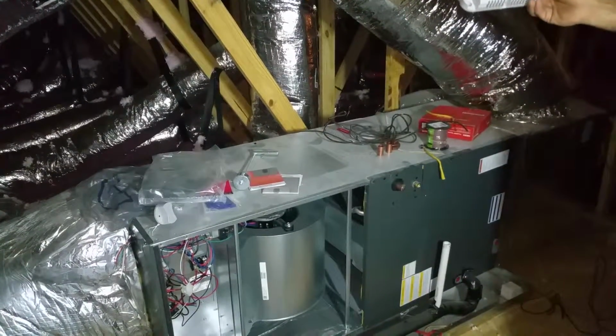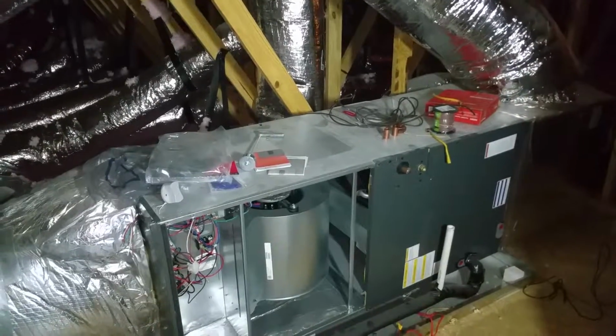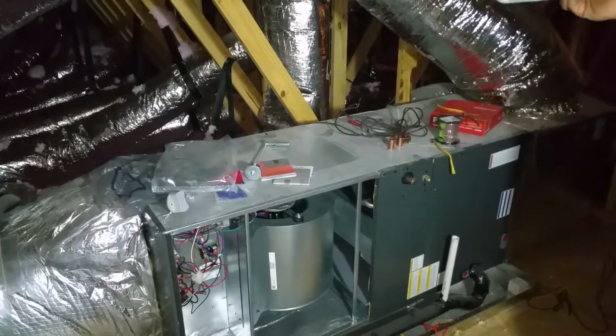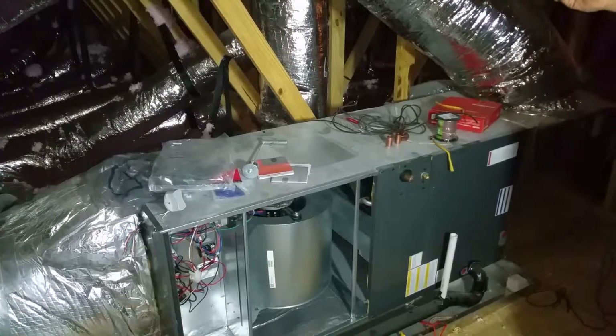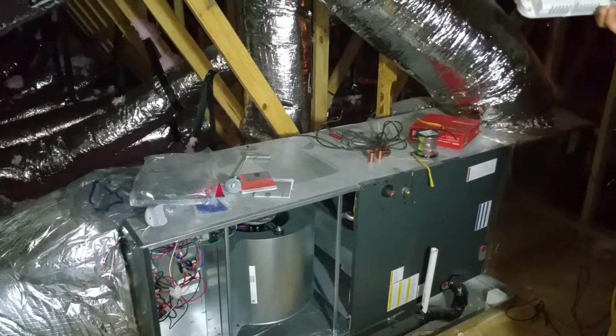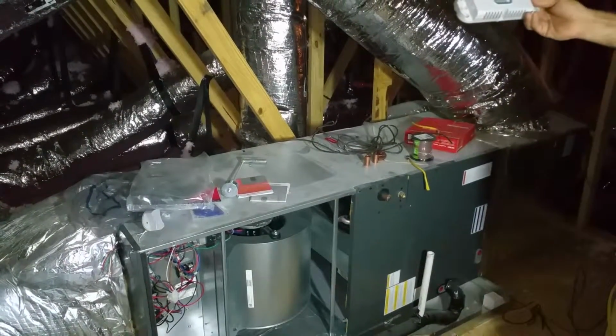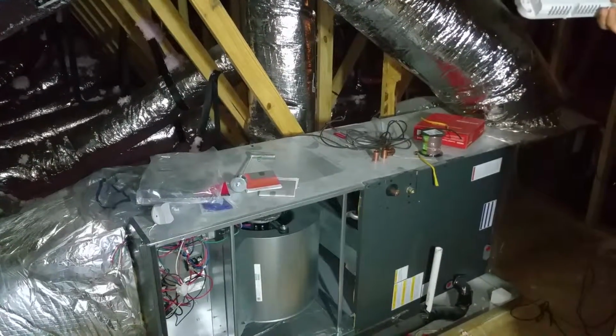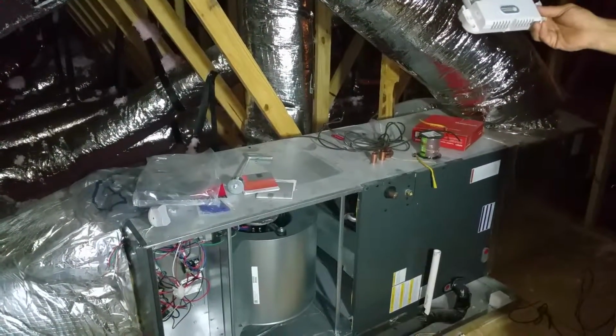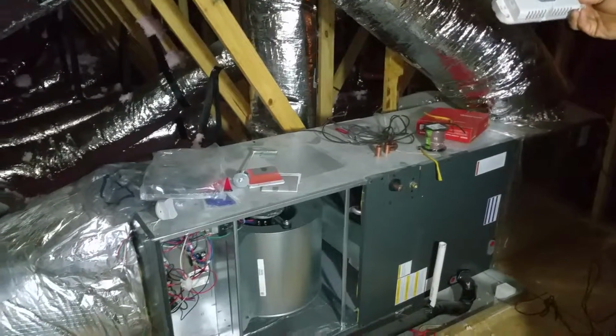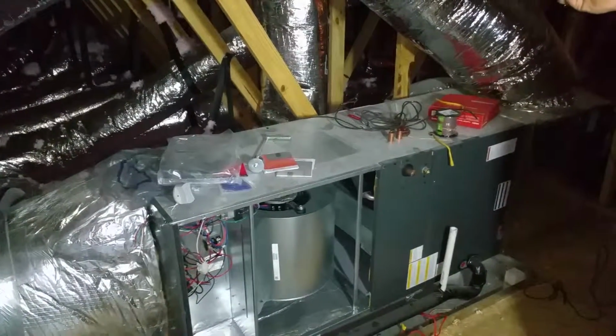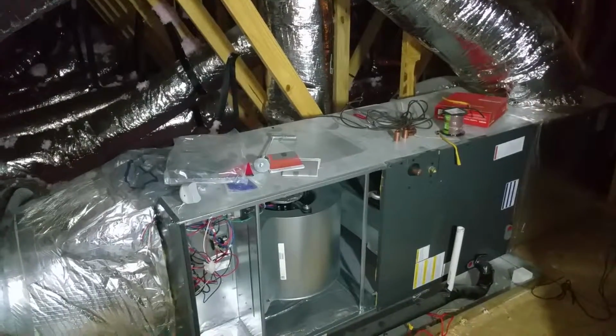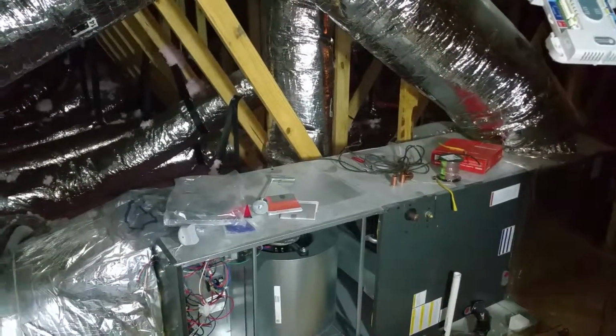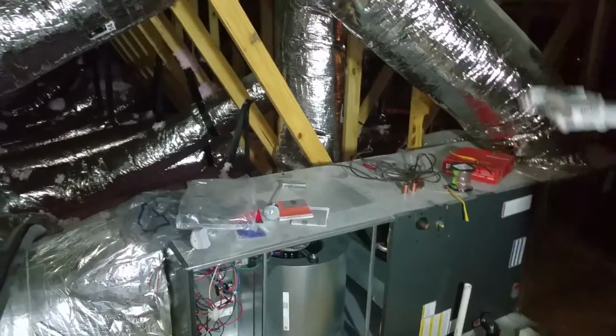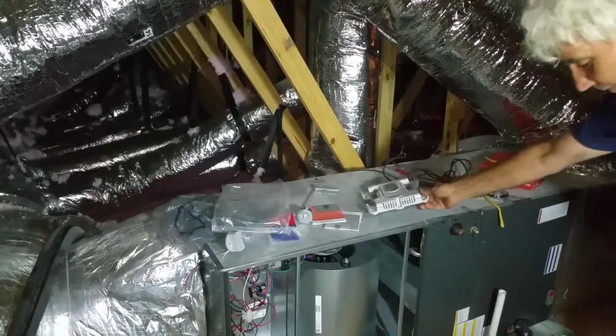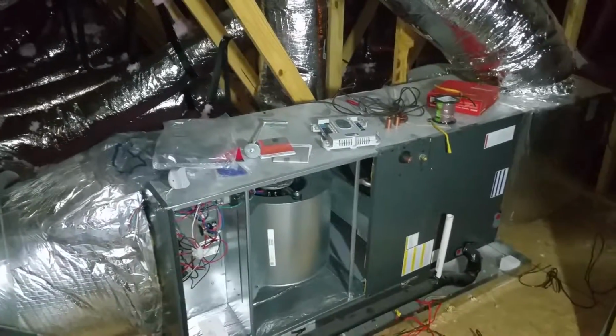2 filters downstairs? Yep, 2 filters, 2 filter grills. In each room, they're both the same size. And they should be changed once a year? No, it all depends on if people have pets or animals. Some people can go up to, I would probably say more like 2-3 times a year. But then you never know. If you have a bunch of cats in the house or something, you might have to change it once a month. Depending, new construction with the, okay. I mean, this really isn't a dusty road. So everybody thinks it's once a year, but it actually should be more often, depending on how many people and what kind of animals you have in the house. But that's it. It's a good system.